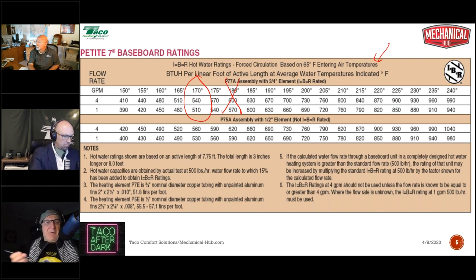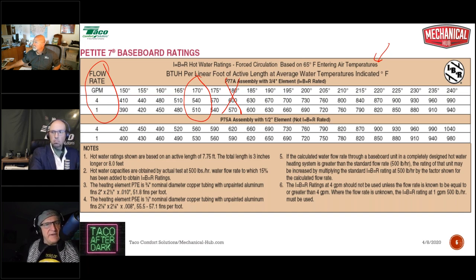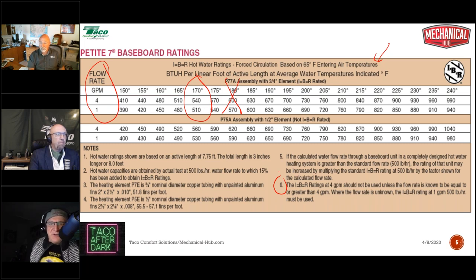So is it a big difference? Oh, I don't know. Let's look at this a little bit further. Now we look and we see that there are two lines here for flow rate, gallons per minute flow rate, at 4 gallons a minute or at 1 gallon a minute. Well, how the heck are we supposed to know which one of those to use? Well, let's take a look. The notes down at the bottom, really interesting things you can find out here. Go right to number 6, all right? And that says the IBR ratings at 4 gallons per minute should not be used unless the flow rate is known to be equal to or greater than 4 gallons per minute. When the flow rate is unknown, the IBR rating at 1 gallon per minute must be used.